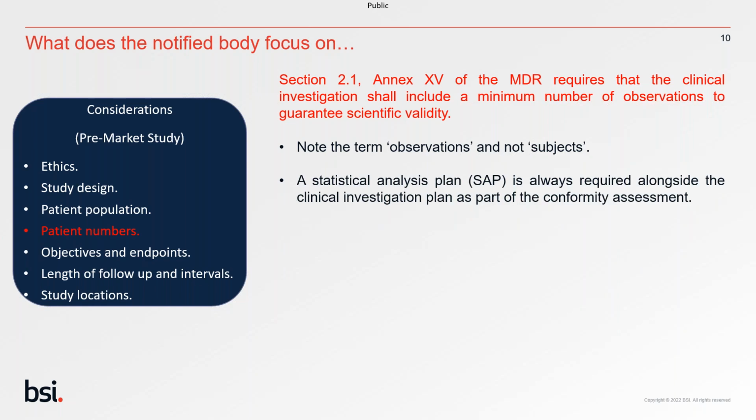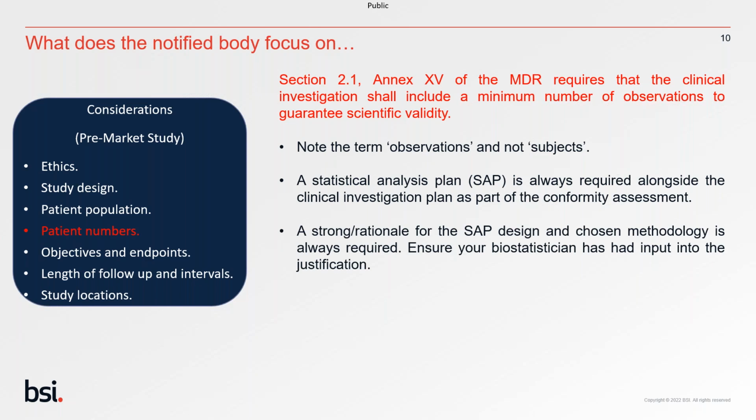Whenever we receive your clinical investigation plan as part of the conformity assessment, we always need to see a statistical analysis plan as well, and it should be provided alongside the clinical investigation plan. It's really important that you provide a strong rationale as to why your statistical analysis plan design has been chosen and the type of methodology that's behind it. Make sure that your biostatistician, for example, has had input into that justification and can clearly demonstrate why you've come up with that particular design.